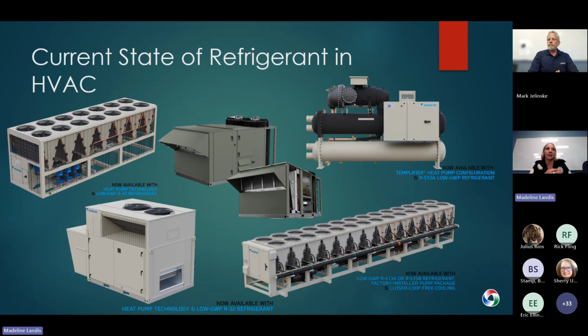Things like centrifugal chillers and things with screw compressors had a little bit of an easier time because the replacement low GWP refrigerant was still an A1, meaning that it was low toxicity and still had a low flame propagation risk. As many of you are aware, scroll chillers and things with scroll compressors had it much more challenging because the replacement for R410A was a new type of refrigerant that had a category of its own because it does have an increased flammability.